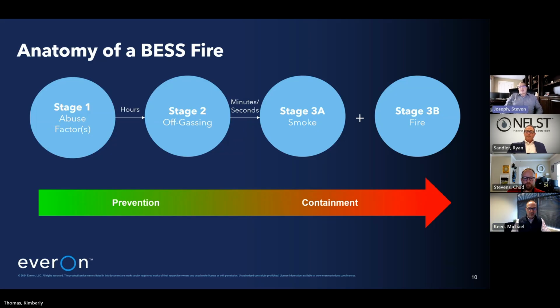And then, we talk about those very early warning smoke detectors. They're also ideal at this stage of development because, we think about that exothermic reaction, things are heating up and smoke particulate is being generated at the incipient stages as a result of that exothermic reaction, heating up materials such as sleeves housing the cells, plastics, and so forth. These can be detected by those incipient smoke detectors, often buying time to initiate automatic shutdown, disconnect power sources via the battery management system. So it's all about management in that respect.